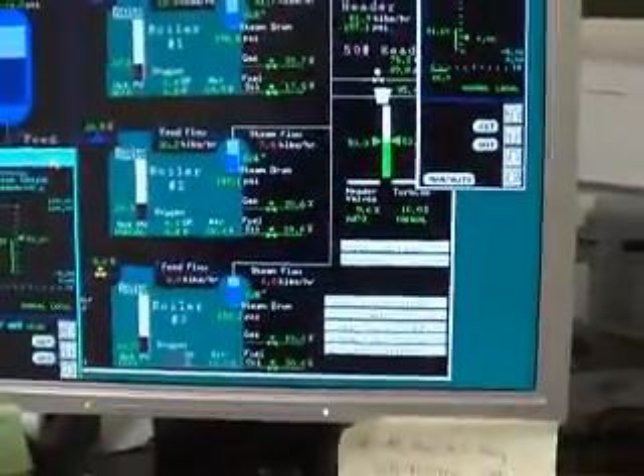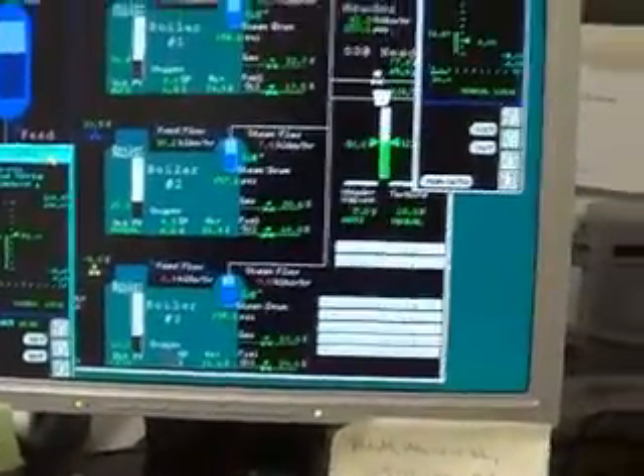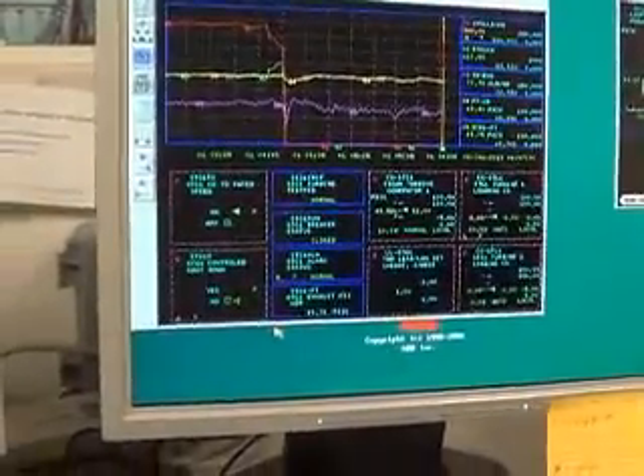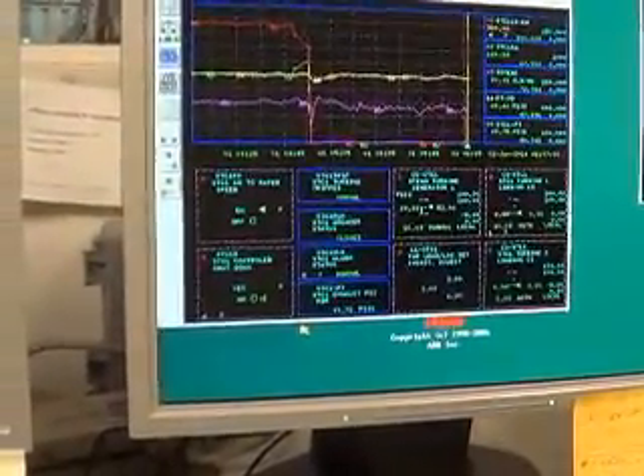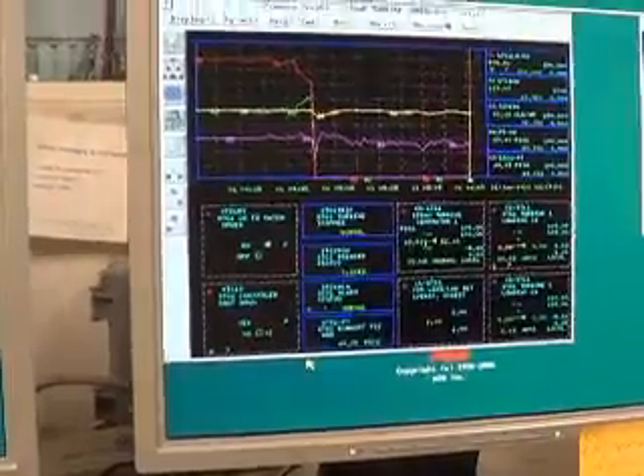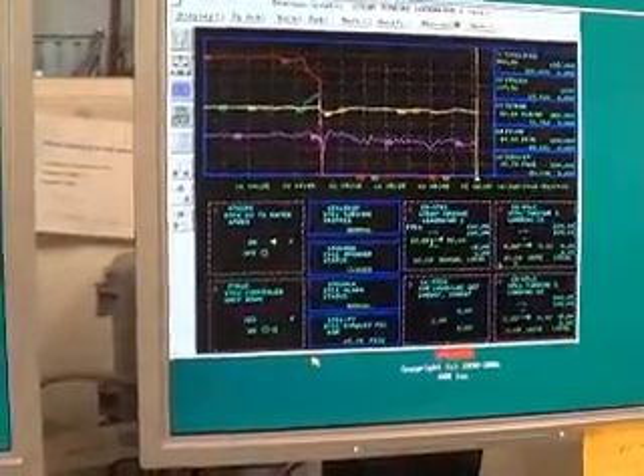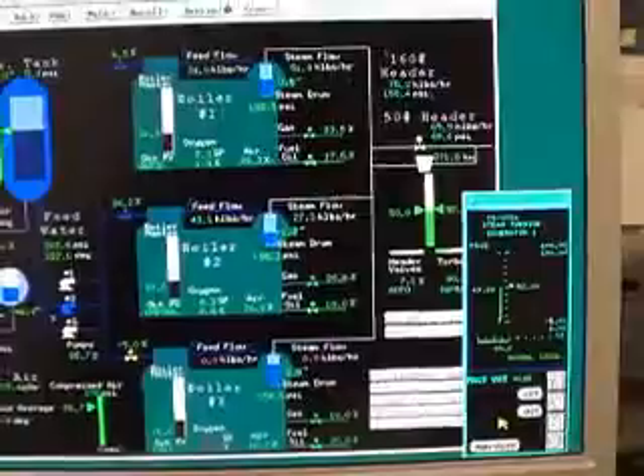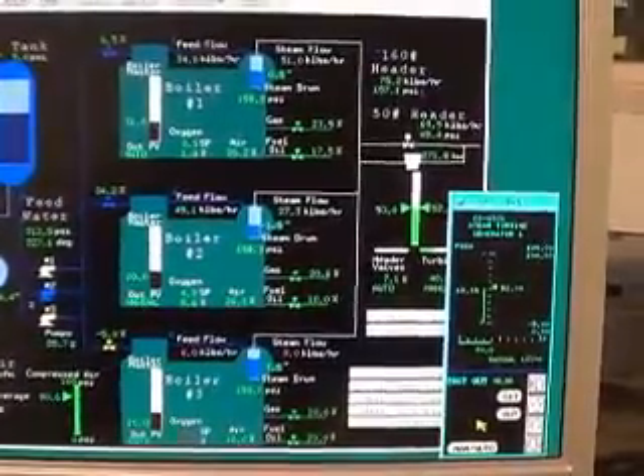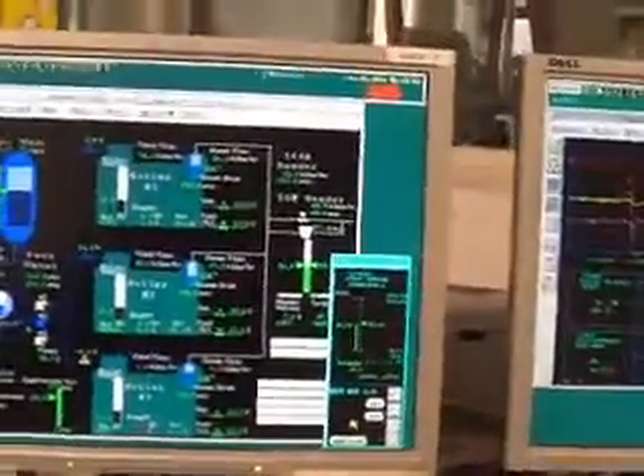Morning. It's first day of 2014 and I'm at work and we're trying to get our turbine running again. Alright, so I went down there and the breaker control, what I did was swap it back into manual control and then back into automatic, and then that's when it went into reverse power. Okay, we're making power. Had a little hitch in the startup.